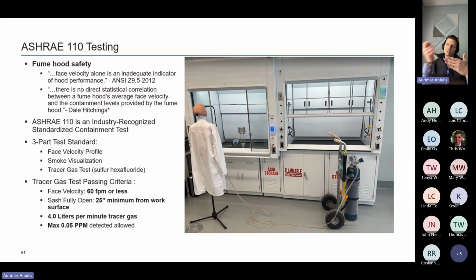Yes, it is. Okay. Now we're going to run some smoke around the perimeter of the fume hood and see, is that smoke actually being drawn into the fume hood? Then they're going to run some smoke inside the fume hood to see if that smoke is actually escaping. And lastly, and most famously, they do a tracer gas test, which uses sulfur hexafluoride. You can see the little flow gauge in the cabinet here and a little diffuser they have in here. And this is Simon, our friendly fume hood dummy tester, with a little probe in his mouth that represents the user's breathing area. The allowable limit is 0.05 parts per million. If you can't contain at whatever face velocity is, you have a problem. You won't pass commissioning, and you won't be able to release the fume hood for occupant use.